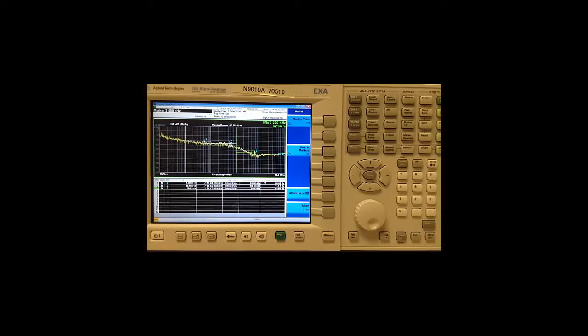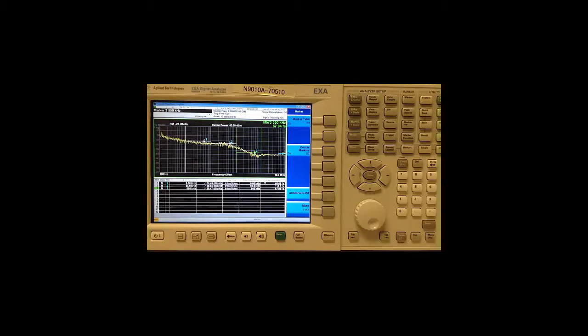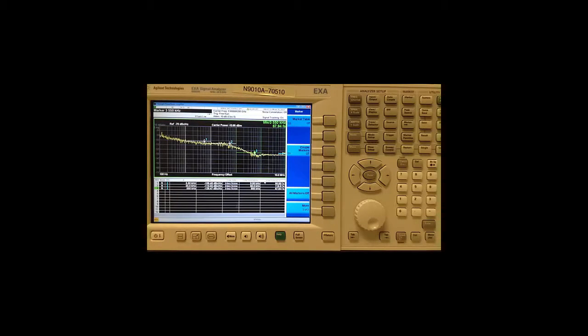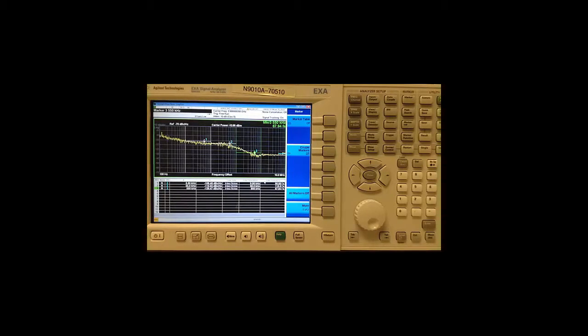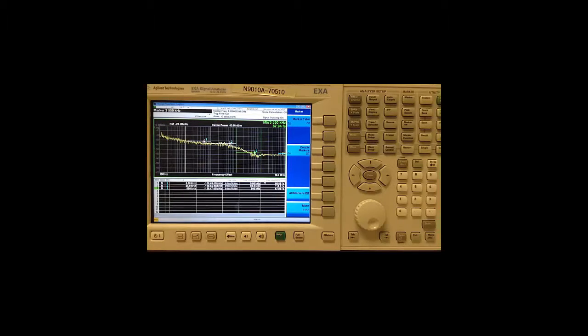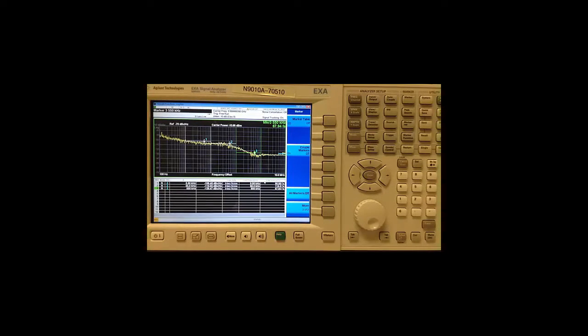Now one common technique in phase noise measurements is to use cancellation which means to make a reference trace and then subtract the reference trace from our measurement. The reference trace can usually be the noise floor of the analyzer or the log plot trace of another signal source which is known to have lower phase noise than the DUT and the analyzer.